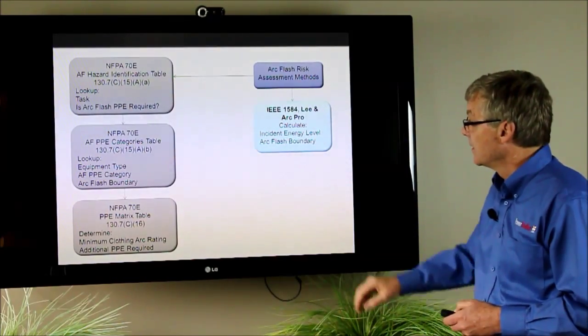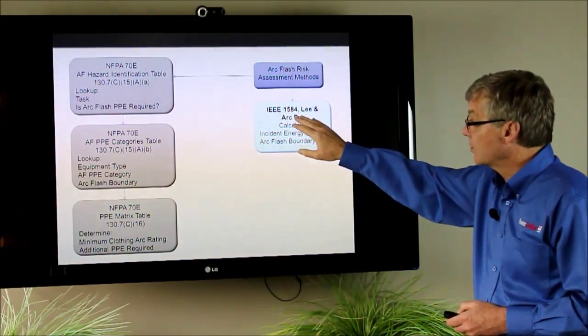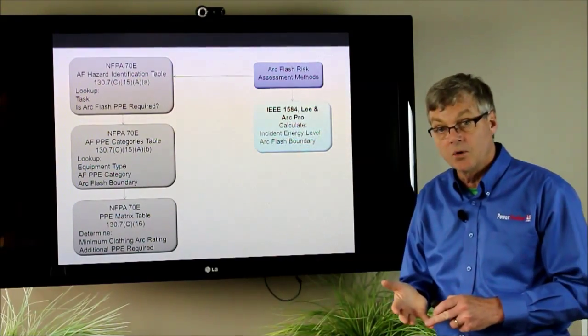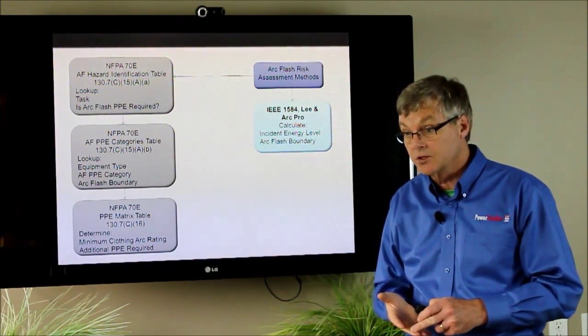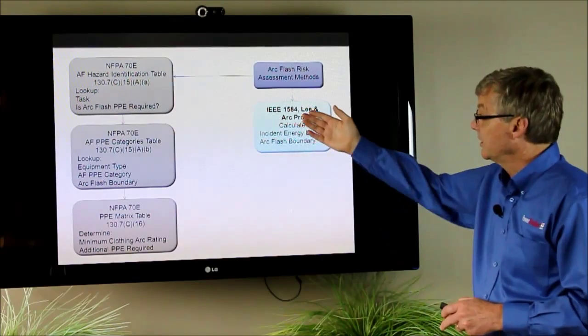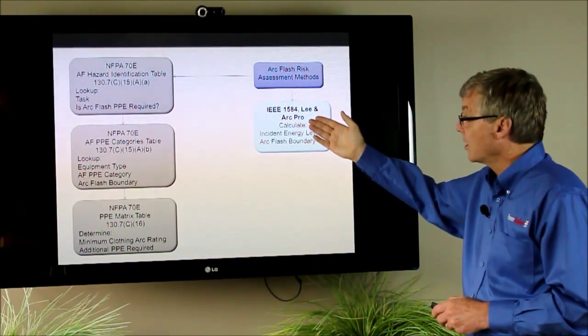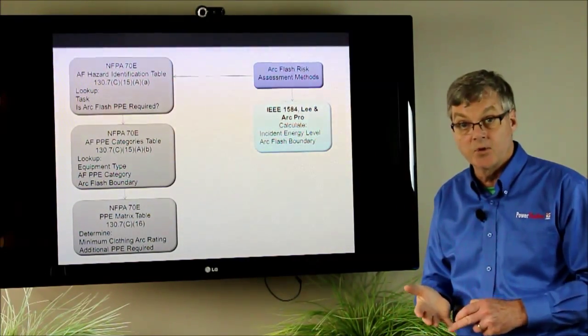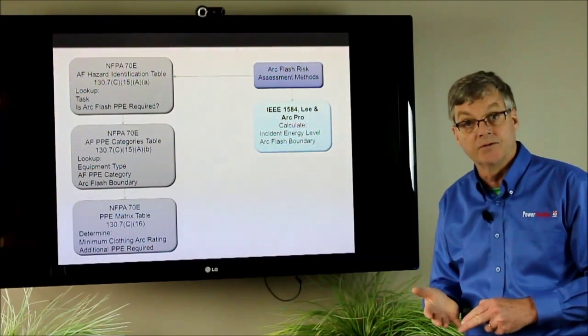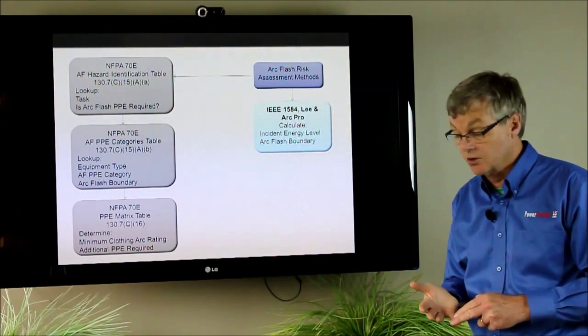And 1584 equations are good for 208 volts up to 15,000 volts. After that you can use the Lee equations, and also arc pro is used quite a bit in high voltage utility type work because it's very good for a single phase to ground faults.